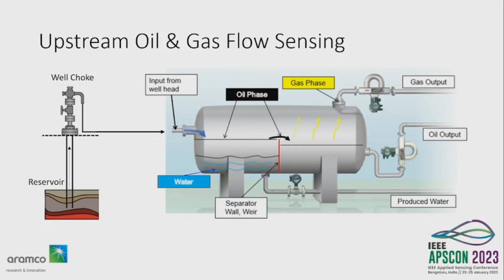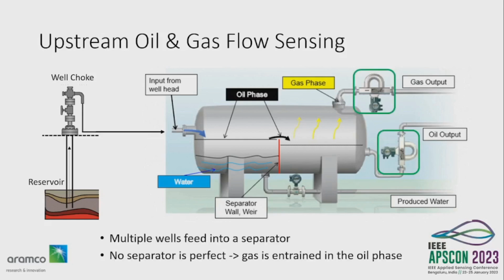Multiple wells like this will feed into a given separator, and each well will produce slightly different hydrocarbons and slightly different amounts of water. None of these separators are perfect, so you end up with some gas entrained in the oil phase or liquid phase, depending on the separator's output. Usually you will use a Coriolis meter at the gas output and at the liquid or oil output. But since no separator is perfect, even in the oil line, the Coriolis meter that's there to meter the liquid will see some gas going through it.